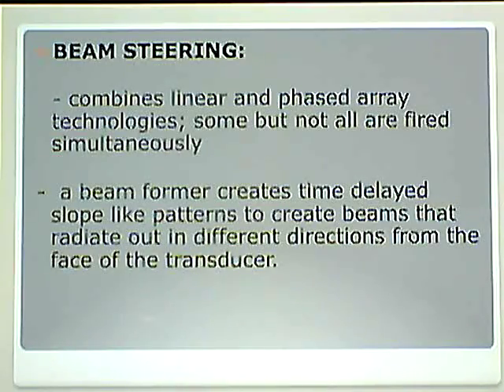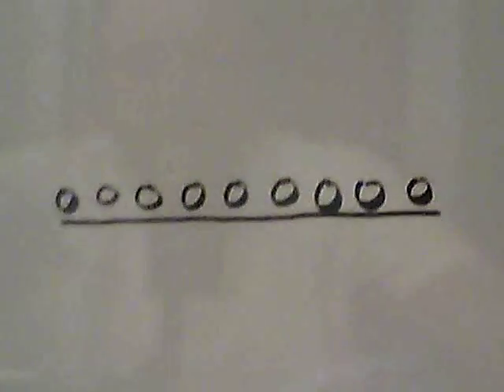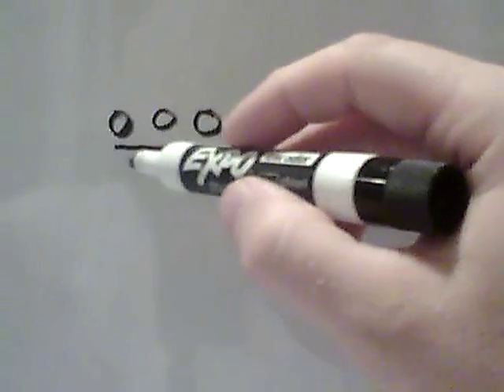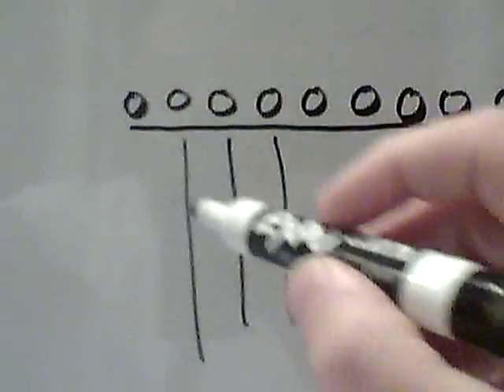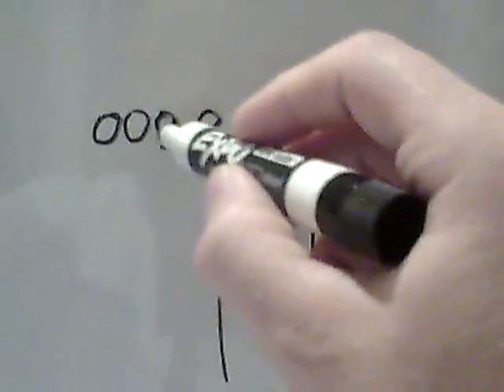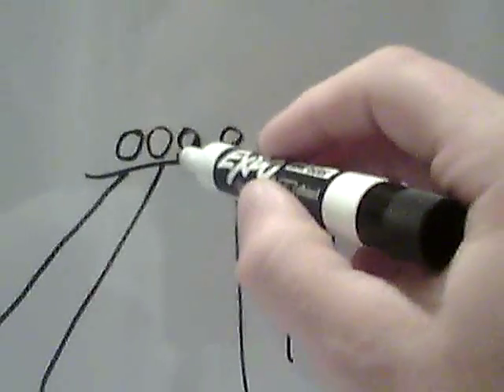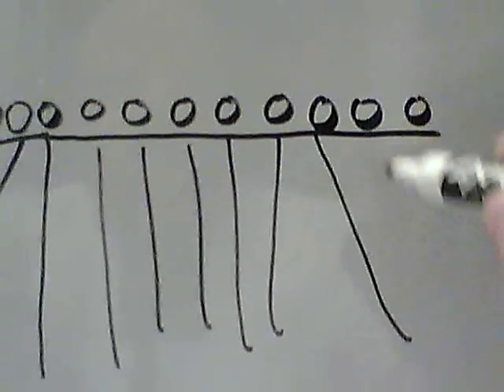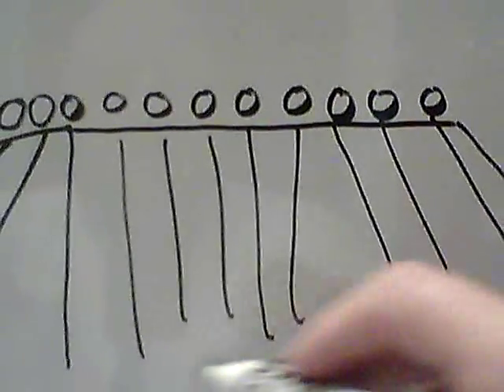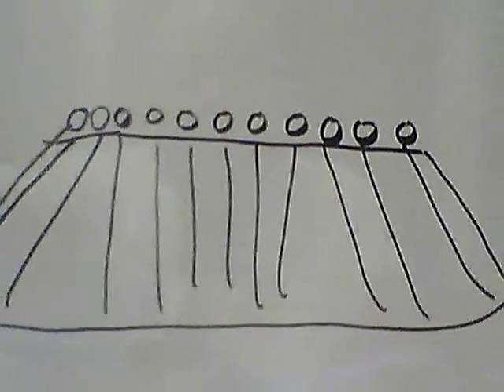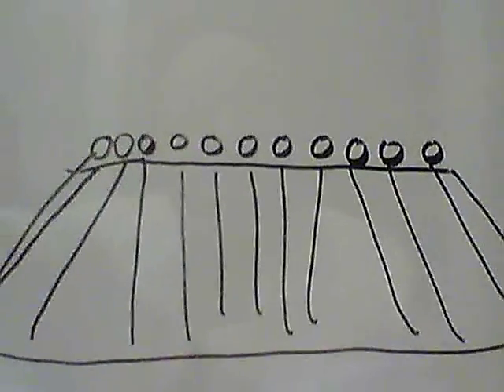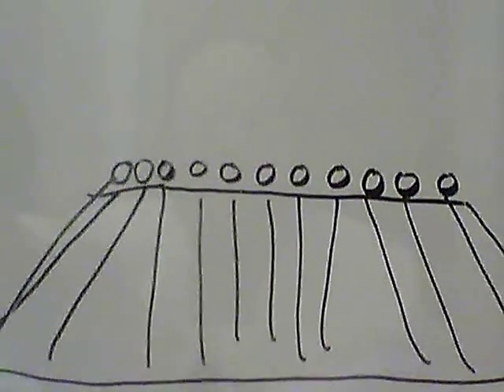This is where the beamformer kind of kicks in a little bit and does a little bit of extra work and gets creative. So if I have these groups of crystals arranged on my transducer, and they're all lined up as such, normally I would fire straight down the line, right? But I'm now telling, let's just draw some extra groups here, these to fire here, these to fire here, these to fire here, and then the last ones steer out this way, and you see now the image shape that I get. So I went out to the side here, straight down, out to the side here. I just use my outer groups of crystals to cover a wider area.